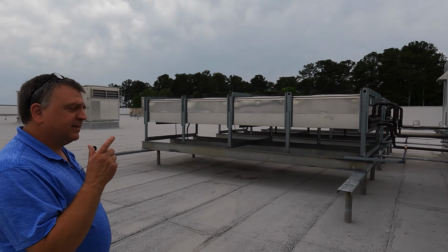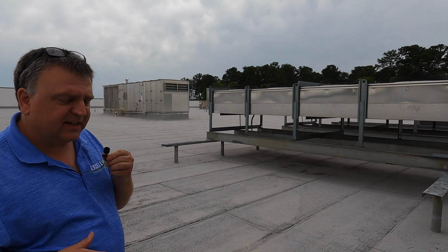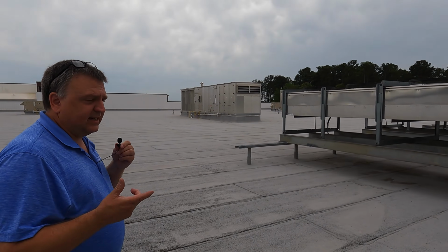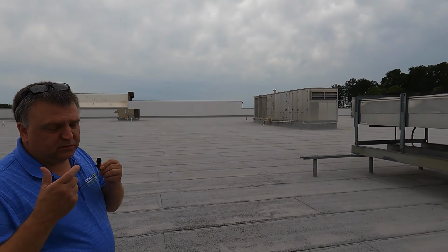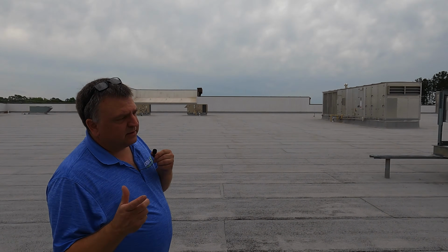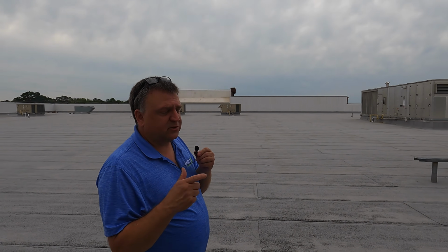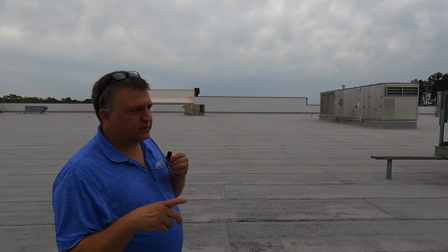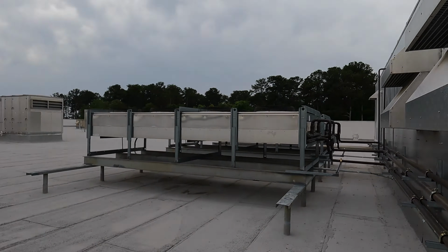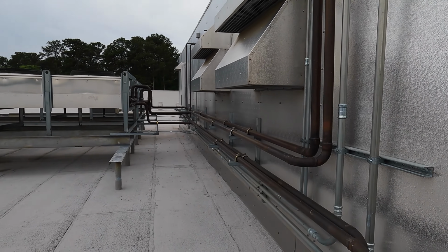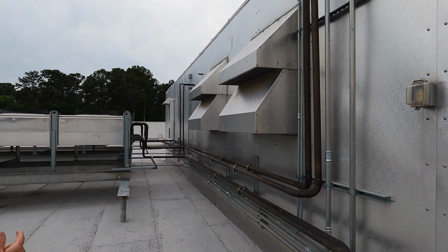Remember earlier I was talking about the de-superheater. It's not really a condenser. A condenser is what it says it is. It condenses from a vapor to a liquid state. The de-superheater just removes extra heat. It doesn't change state. The condenser is what changes the state of the refrigerant. So we have high discharge, high temperature gas going into our condensers and coming out a high pressure liquid.